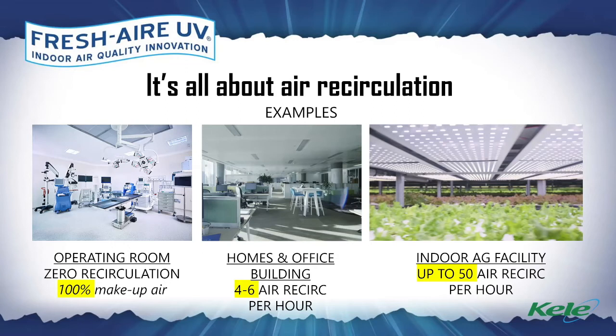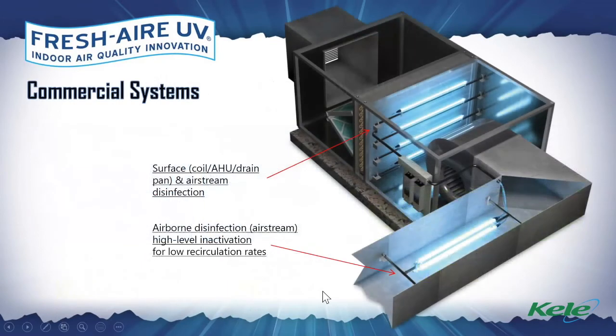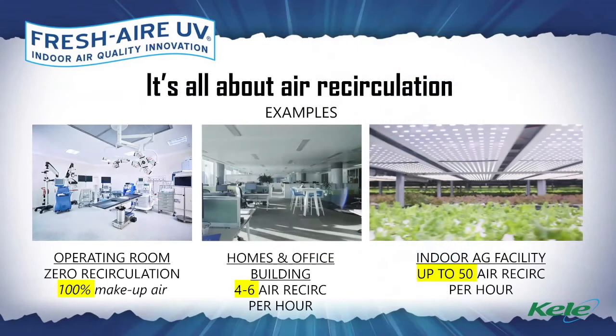So if we're doing a healthcare facility, where we have to guarantee a very high log reduction on one pass of air, then we're going to go with that parallel orientation to airflow. That duct mount unit could range from 2 lamps to 6 lamps, from 18 inches to 60 inches. They're sized according to duct dimensions and CFM and the desired biological inactivation rate. But that's for those hospital grade air quality applications.